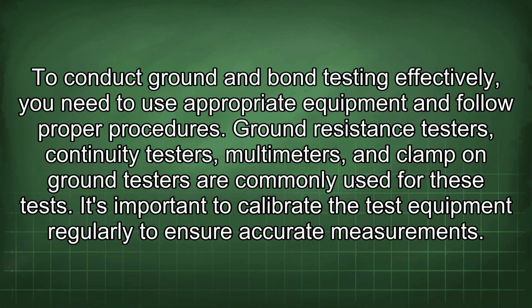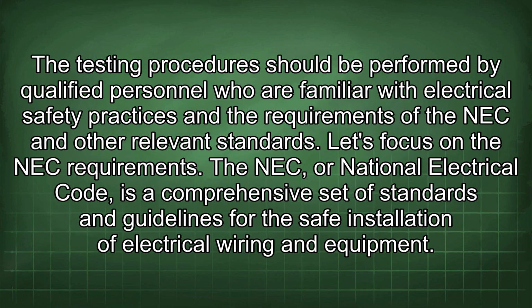To conduct ground and bond testing effectively, you need to use appropriate equipment and follow proper procedures. Ground resistance testers, continuity testers, multimeters, and clamp-on ground testers are commonly used for these tests. It's important to calibrate the test equipment regularly to ensure accurate measurements. The testing procedures should be performed by qualified personnel who are familiar with electrical safety practices and the requirements of the NEC and other relevant standards.